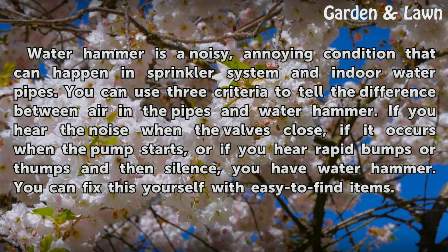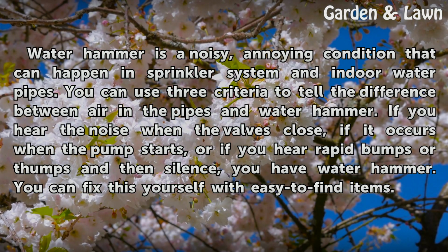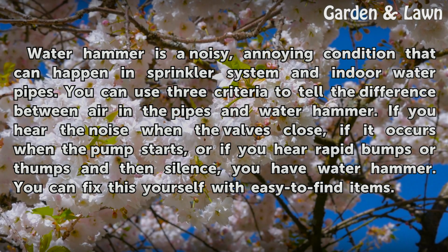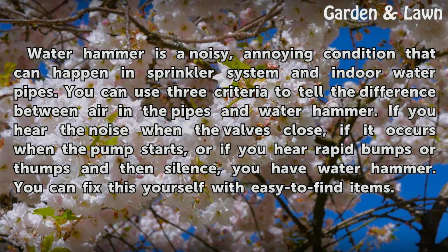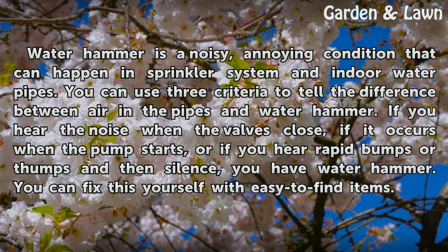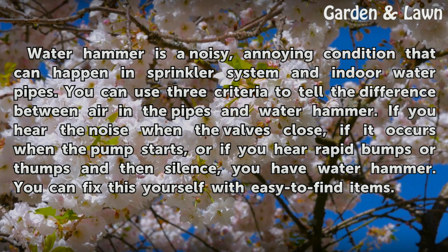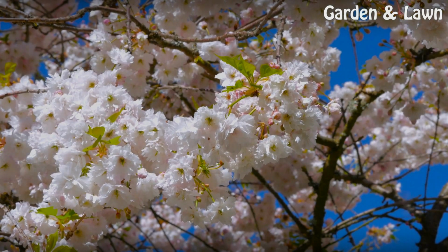You can use 3 criteria to tell the difference between air in the pipes and water hammer. If you hear the noise when the valves close, if it occurs when the pump starts, or if you hear rapid bumps or thumps and then silence, you have water hammer. You can fix this yourself with easy-to-find items.